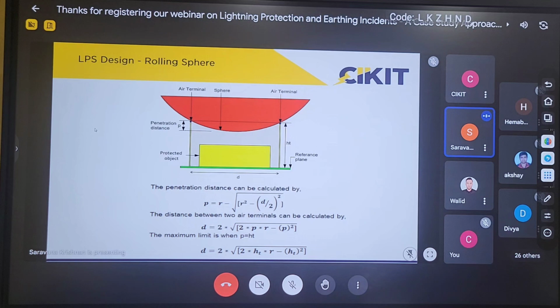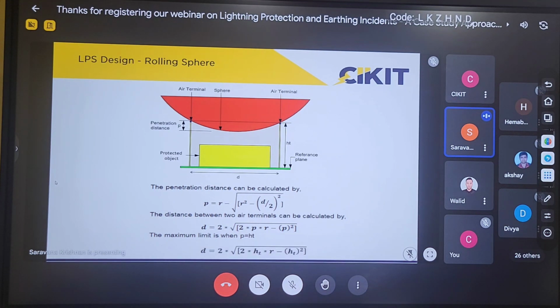If I want to calculate the distance between two air terminals, then I can use the second formula: D is equal to 2 into square root of 2pr minus p square. It includes two parameters. One is the radius, which depends upon the level of protection, and the second one is the penetration distance. The penetration distance is nothing but the distance up to which the sphere goes below the level of the air terminal. You can observe from the above image that the penetration distance is marked as the distance where the bottom portion of the sphere comes below the level of the air terminal.